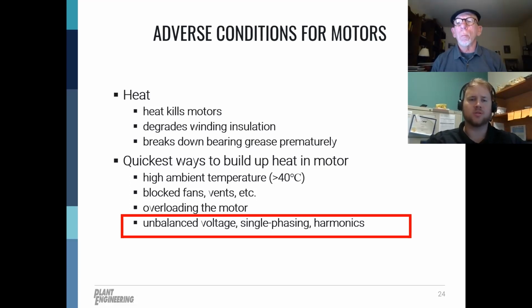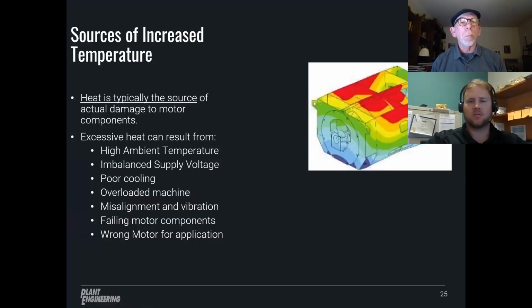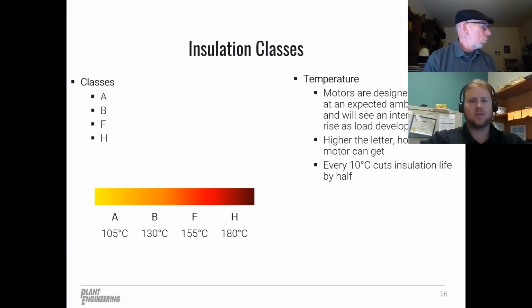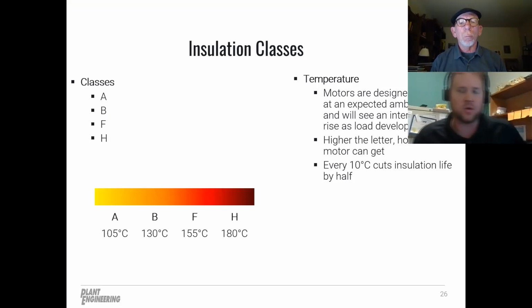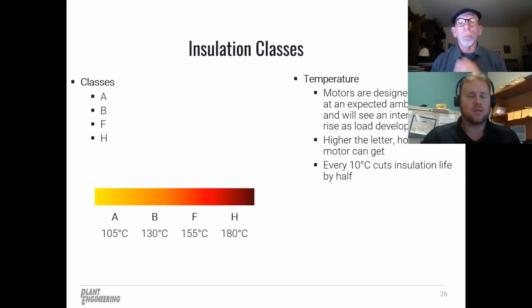But what are some sources of increased temperature? When we talk about heat, heat is typically the source of primary damage to the motor components. And excessive heat occurs from the things that we just talked about, along with some other things: motor vibration, incorrect motor sizing, and then what we talked about earlier, elevated ambient temperature. It really depends on the application. When we talk about heat and motor temperature, it's kind of a general topic. You may wonder, all right, what operating temperature is appropriate for a specific motor? Because you're going to have applications operating at 120 C, and other applications where the motor's running at 50 C. What is appropriate for your application for a specific motor? How do you decide what number makes sense?